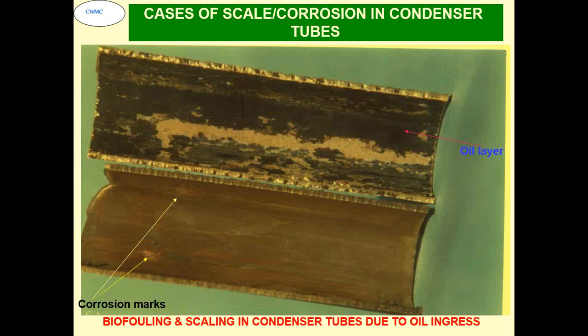Now this was a typical case where the water was supposed to be corrosive in nature, but all of a sudden the plant reported they had a 1 mm thick calcium carbonate scaling. When we analyzed the problem, we found there was a black layer, what you see on the top tube, that was caused because of the oil in the water. So oil formed a film that changed the heat transfer characteristics, and the water which was supposed to be corrosive in nature, even with that low scaling tendency, a heavy scale had formed in a short while. So the outcome is we have to ensure that no oil comes into the cooling water system.